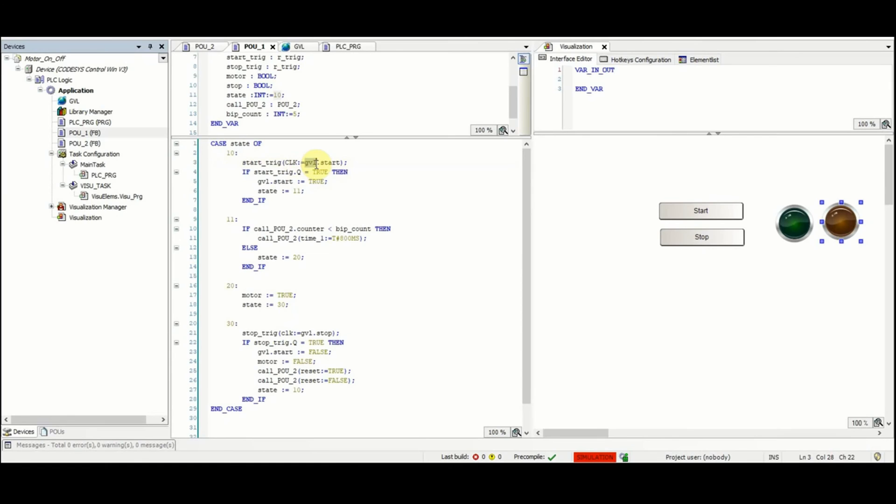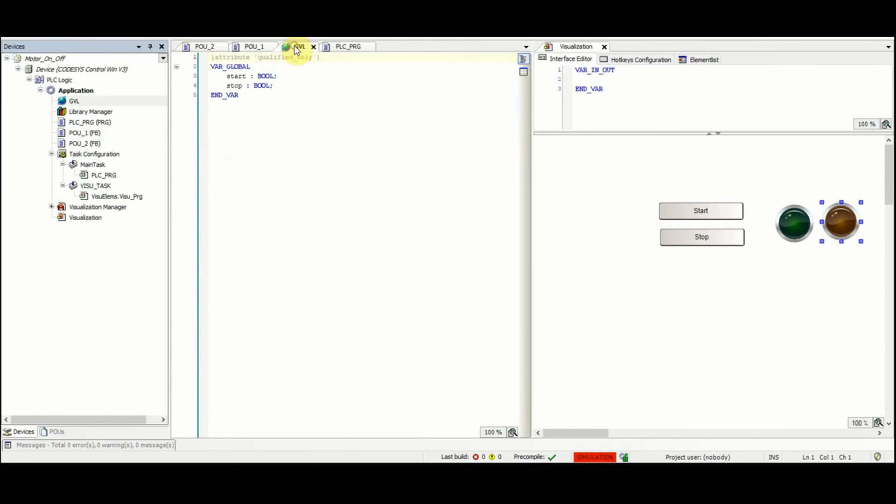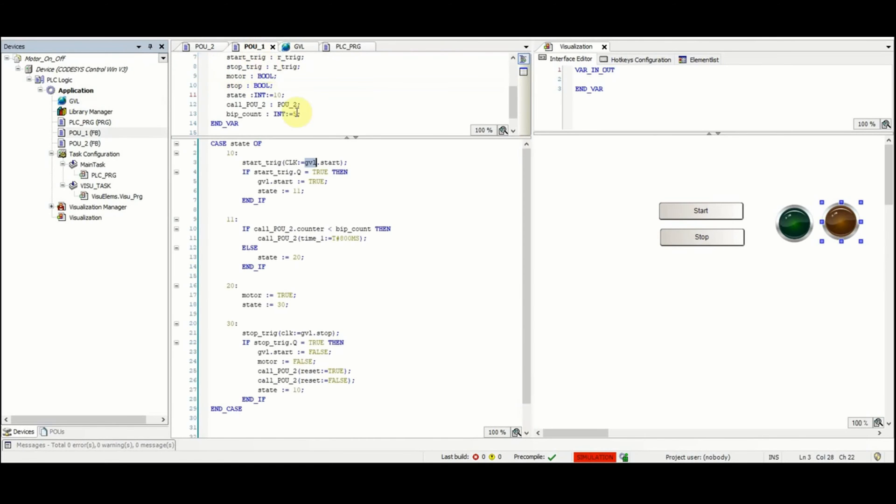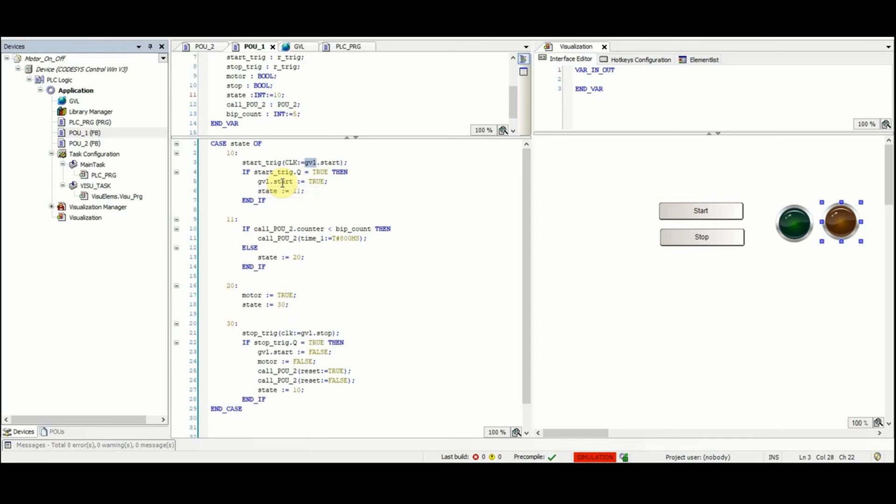As global variables we have two variables start and stop, both of them are boolean. And then the output of the start_trig function block is checked which is Q. If it's equal to true then the start variable is set to true and then the state is changed to 11.